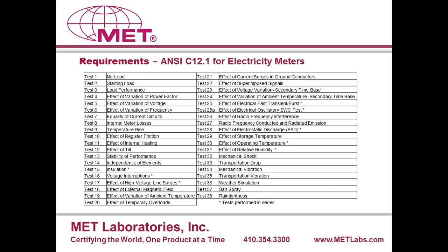But it's important to note that the same 3 samples need to go through these 8 series tests. So you're not only looking at whether the meter meets the criteria of those individual tests, but you're also looking at accumulated stress. Does that become a factor as you run through those 8 tests? Whereas with the other tests, you're allowed to use different samples. Same build of meter, but different sample sets can be run concurrently. And that really helps expedite the testing program.